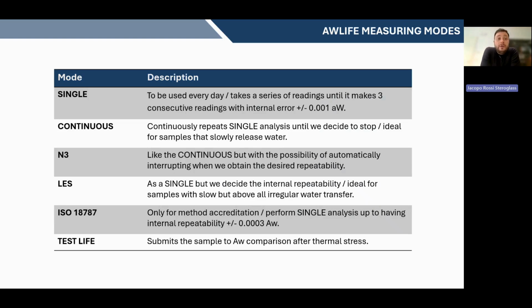You can have different ways to achieve the result. You may consider that in 90% of cases you're going to run the single method. The single method is simply a reading that will stop automatically when you have 3 consecutive readings with an internal error of 0.001. It means that when the plateau is reached and the balance is achieved, it stops automatically.